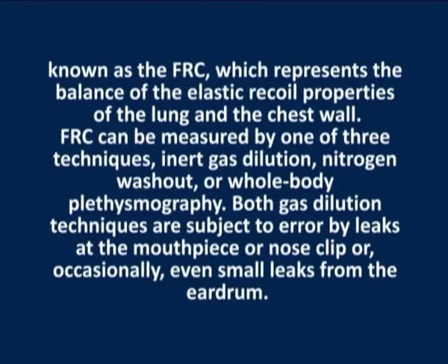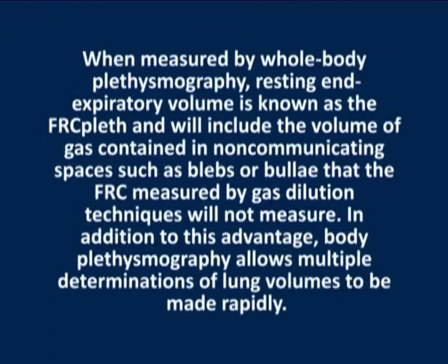FRC can be measured by one of three techniques: inert gas dilution, nitrogen washout, or whole body plethysmography. Both gas dilution techniques are subject to error by leaks at the mouthpiece or nose clip, or occasionally even small leaks from an eardrum.